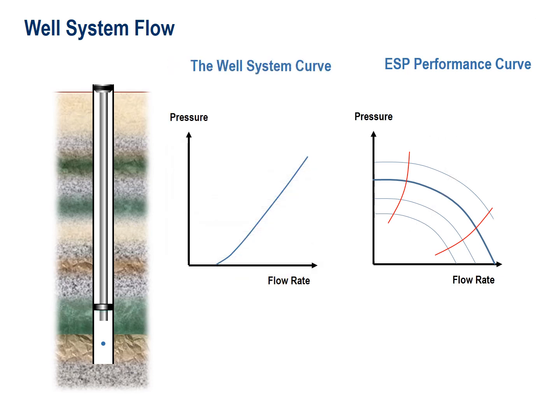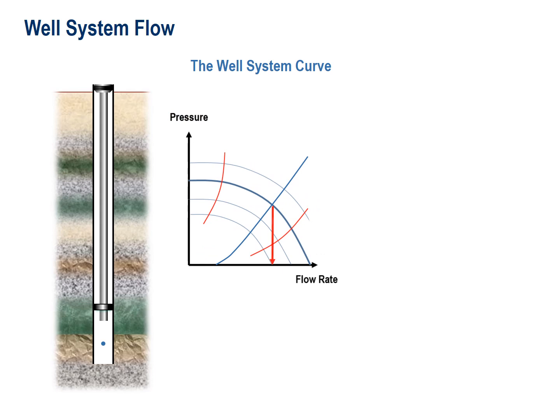So now we have the amount of artificial lift our well needs as a function of flow rate, and the amount of artificial lift our pump can provide as a function of flow rate. We can cross-plot this to find the flow rate that our total system can deliver — and here we see the so-called operating point, and again the red arrow.